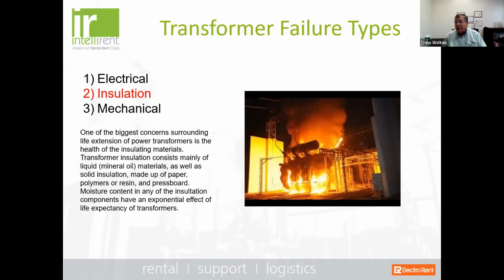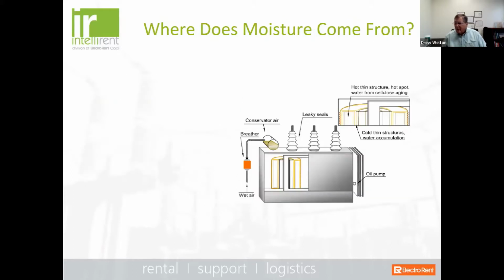So one of the biggest concerns surrounding life extension of power transformers is the health of the insulating materials. Transformer insulation typically consists of liquid like mineral oil and solid insulation made up of pressboard, polymers, or resins. And moisture content in any of these insulation components has an exponential effect on the life expectancy of this device. Okay, so where does moisture come from?